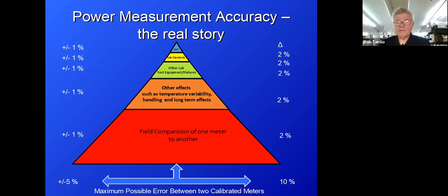So plus 60 dBm would be 1 kilowatt. So if you use 60 dB of loss, for example, that means that you're going to measure 1 kilowatt full scale. What's coming out of the coupler will be 60 dB down from that, or 0 dBm. So if we take that 0 dBm signal from the signal generator and we carefully look at that, we can tell how close to 1 kilowatt the meter will actually indicate. Our standard is plus or minus 1%. We generally come well within 1% of the calibration standard. So, okay, that's part of the calibration.